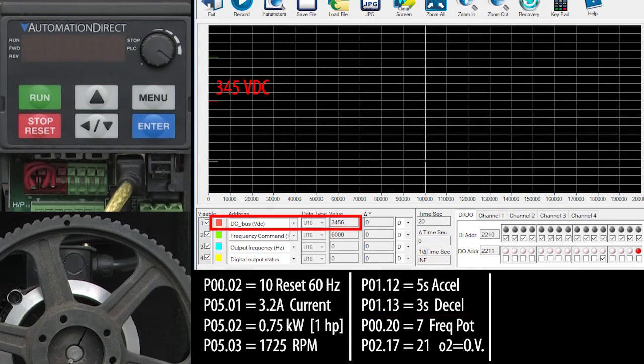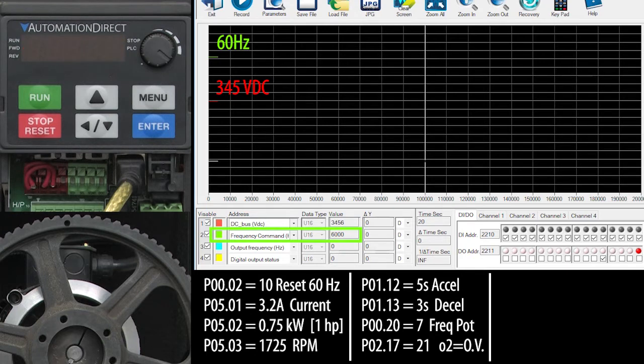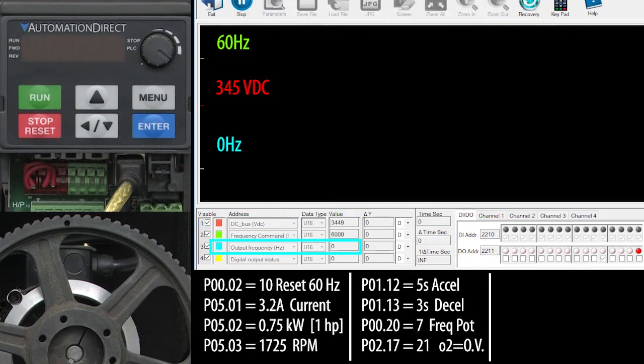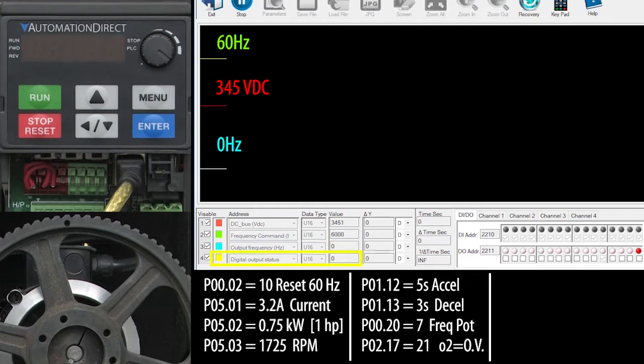I'm monitoring the DC bus with the red trace, the desired or commanded frequency with green, the output frequency to the motor with blue and the overvoltage signal with yellow.